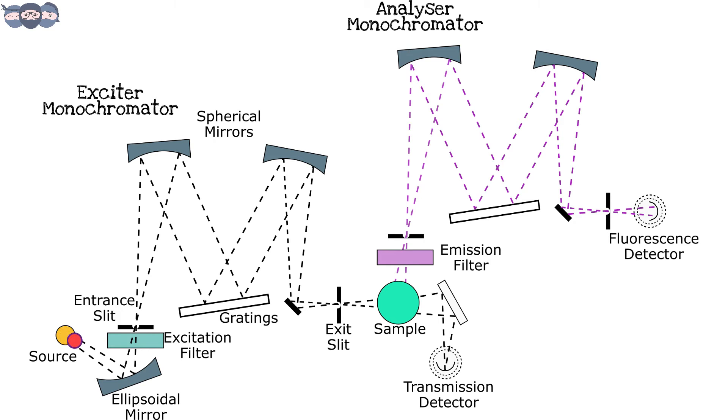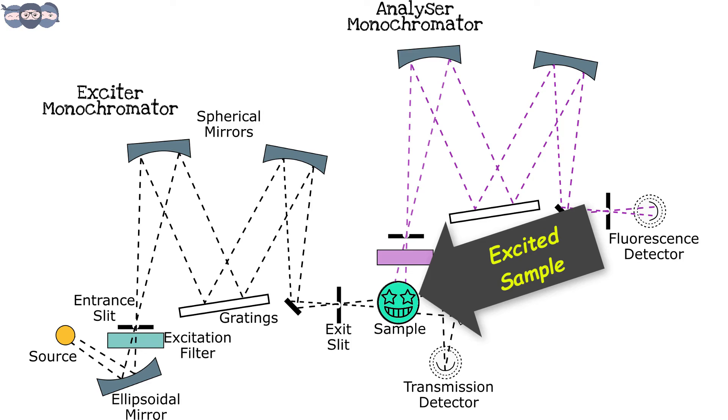Coming to working, we can see that the light from the light source passes through an exciter monochromator. Here only the required wavelength of light passes through the exit slit. This incident light is absorbed by the sample or the analyte. The remaining light gets transmitted and falls on the transmission detector.